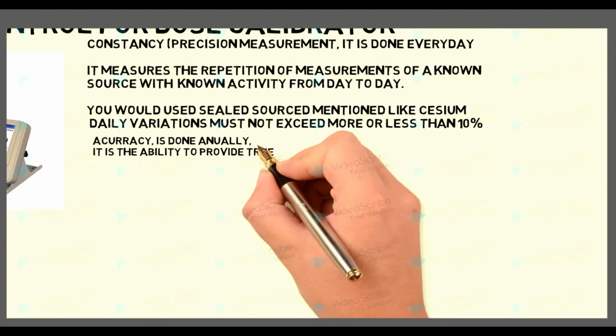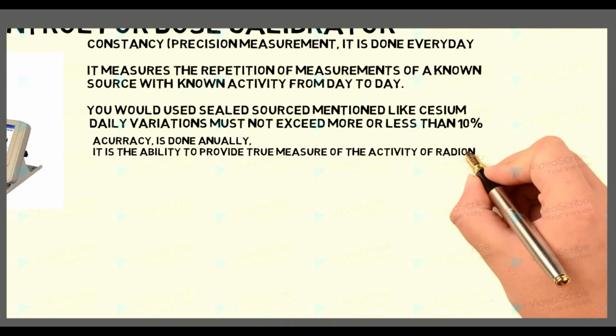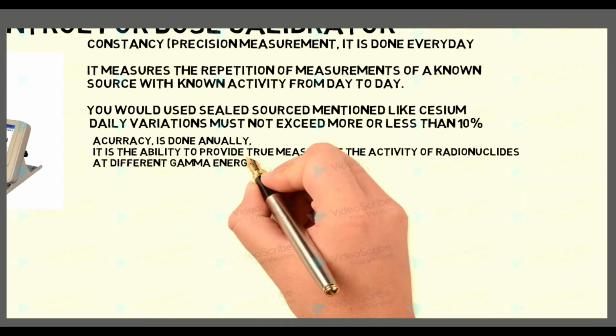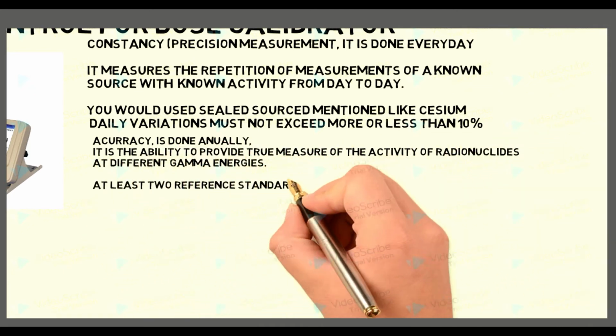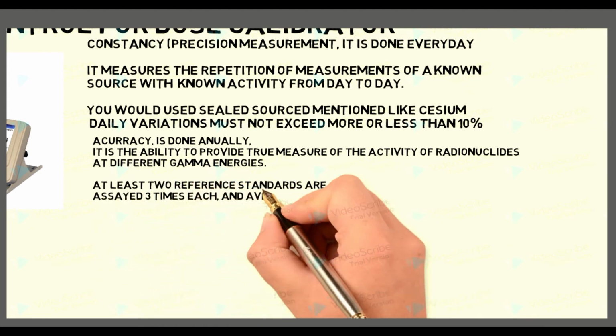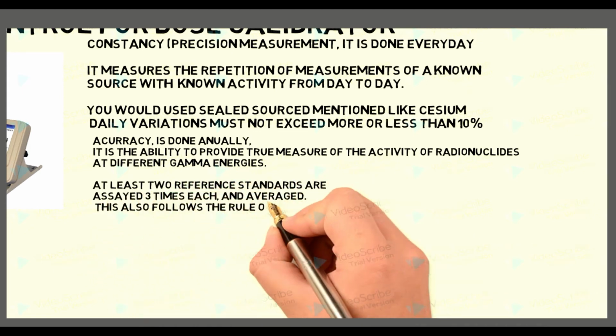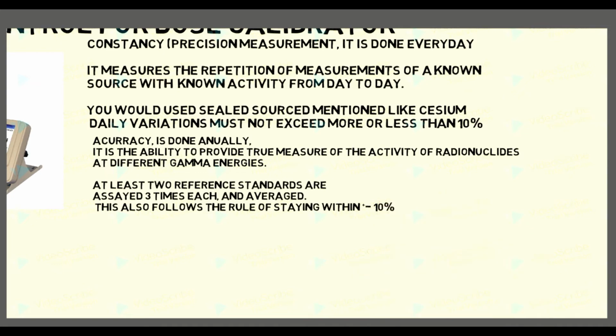Accuracy is done annually. It is the ability to provide true measure of the activity of radionuclides at different gamma energies. At least 2 reference standards are assayed 3 times each and averaged. This also follows the rule of staying within the 10% window.